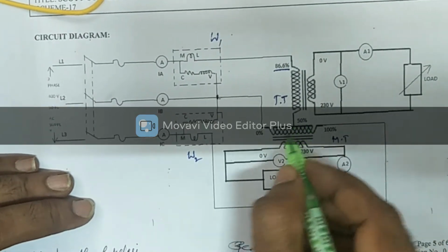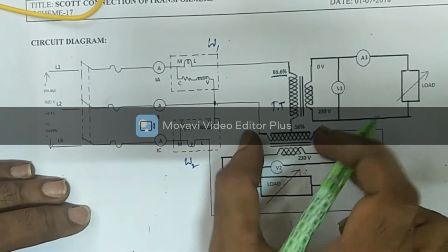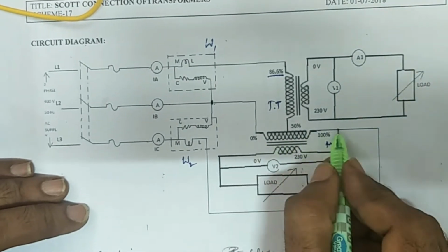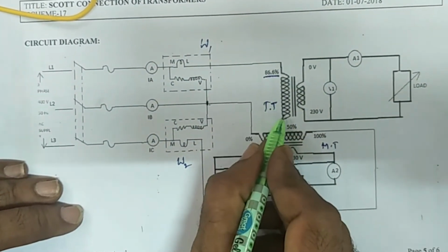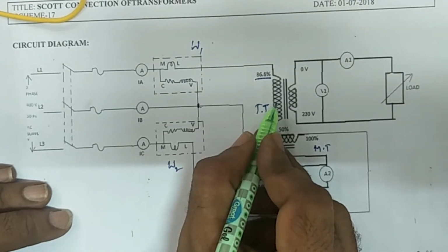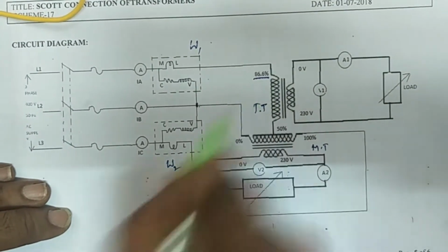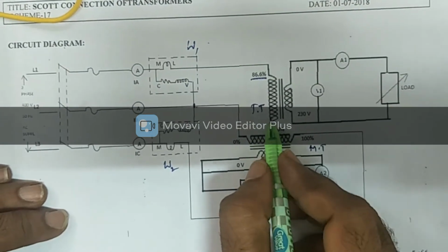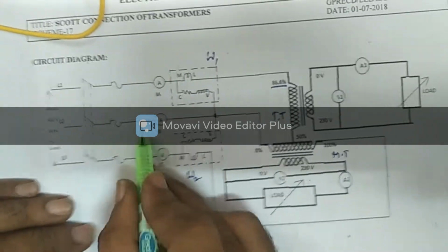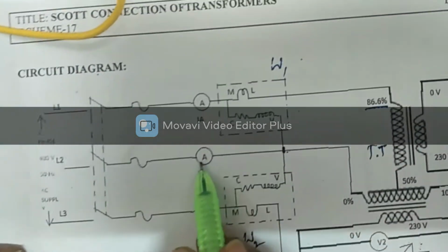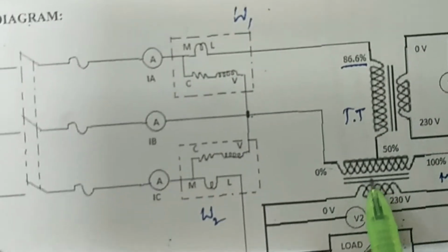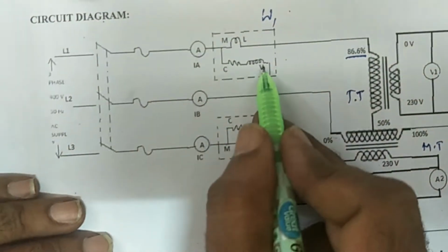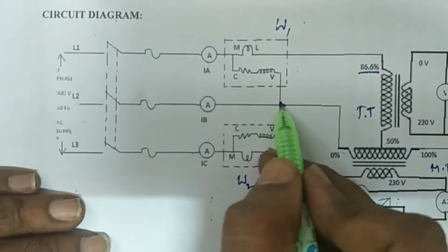Clear? The other end of the teaser transformer, that is the 0 terminal, is connected to 50% of the turns of the main transformer primary side. This is the main transformer primary side, and this is the teaser transformer primary side. On the primary side of the teaser transformer, please remember 86.6% of the turns is to be considered, and the other end of the teaser transformer is connected to 50% of the main transformer. Now the second terminal L2 is connected to the ammeter common, then the ammeter's other end is connected to 0% of the main transformer, and the V connections of the two wattmeters are joined together and then connected to 0% of the main transformer.